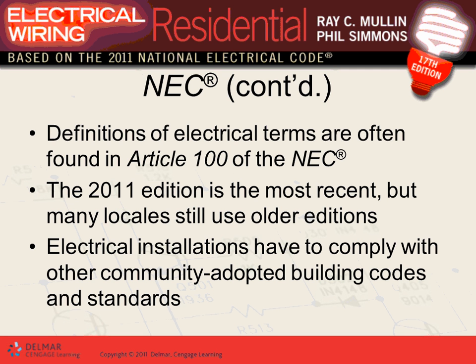The Americans with Disabilities Act requires you to put the height of receptacles and switches between certain values. Why do you think they do that? That's not the NEC code book. The NEC code book cares less, you can put your switch as high as you want, except there's a limit of 6'7" on disconnects.